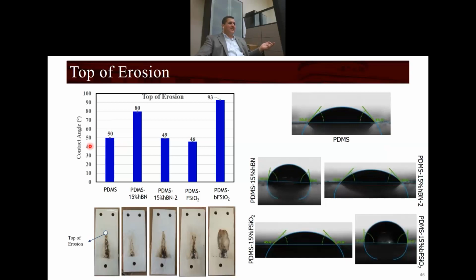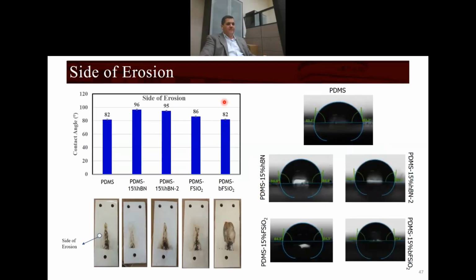This test was done in maybe not more than 4 hours until you reach that 4.5 kilovolt. But it lost its hydrophobicity compared to something like fumed silica, for example. And this is a very important point to take into consideration. At the side of the erosion, also nothing much really happens, and it's because it does not get exposed to the electrical charge as much.